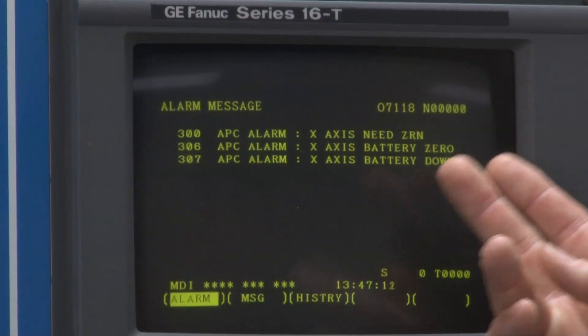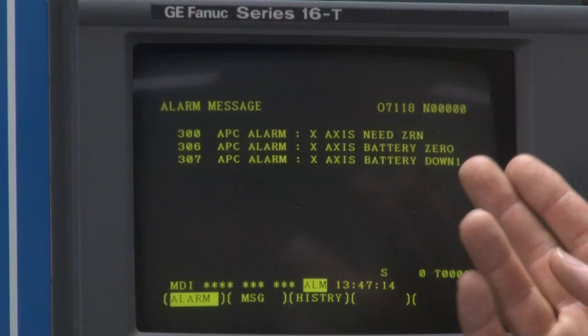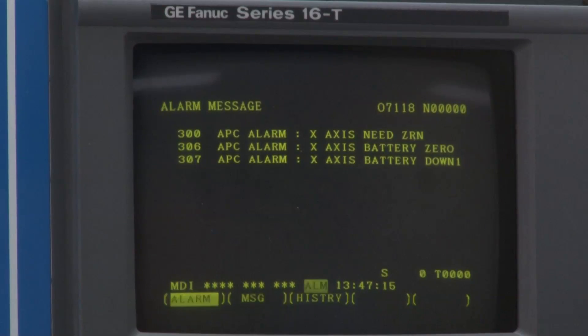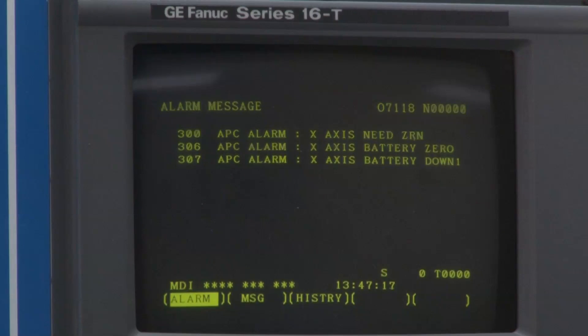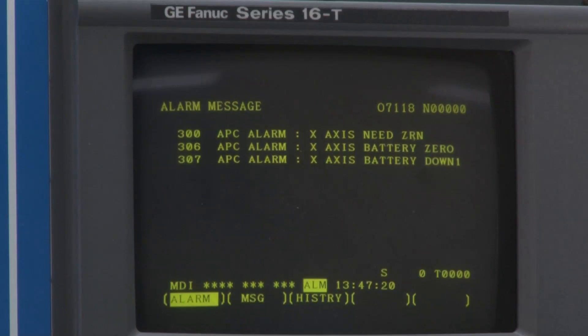If, however, you lose the memory retention due to an encoder cable being unplugged, then you will end up with the 300 level alarms. These alarms are simply saying that the machine must be re-referenced. The referencing procedure will be determined by the machine tool builder — consult your machine tool builder manual for the proper operation.